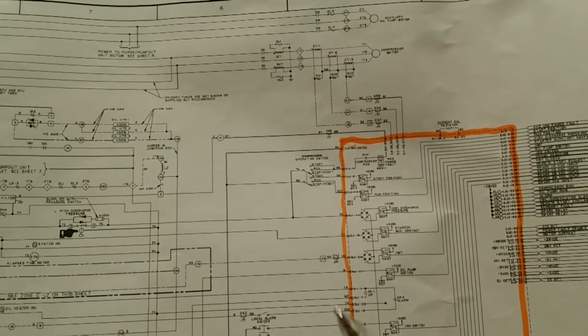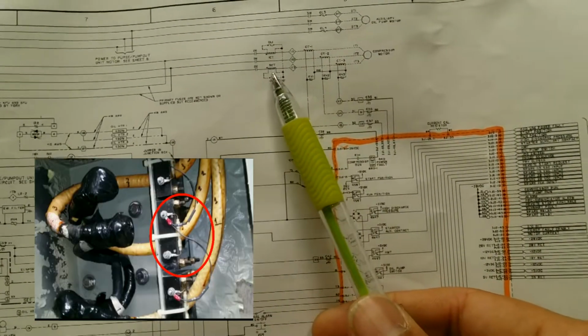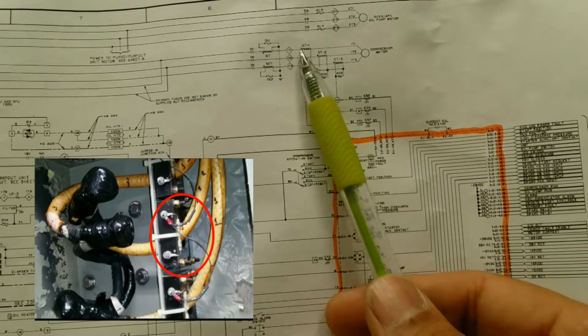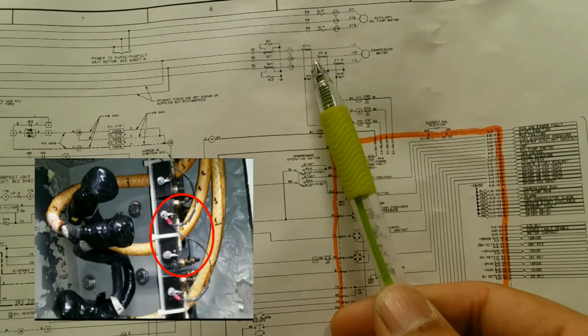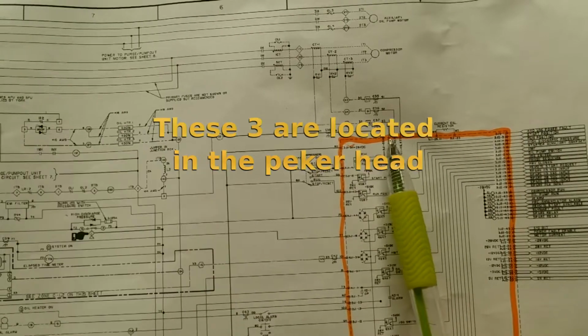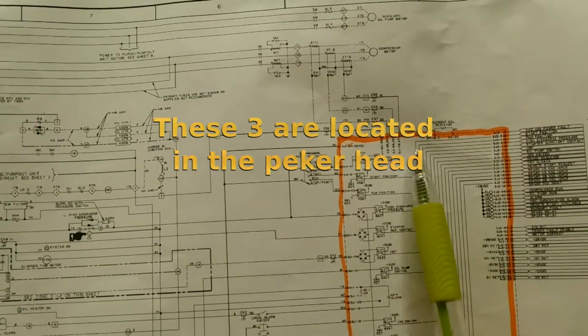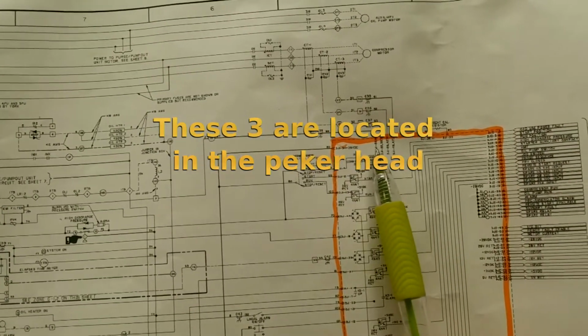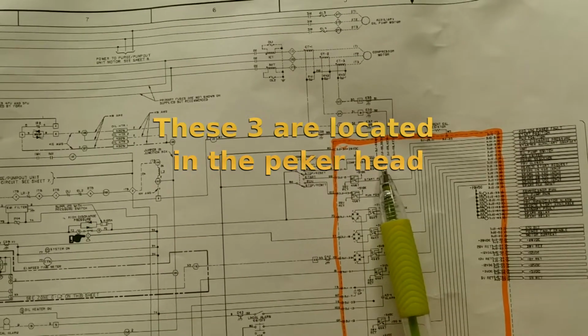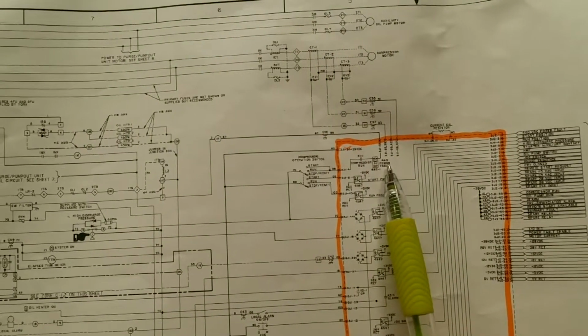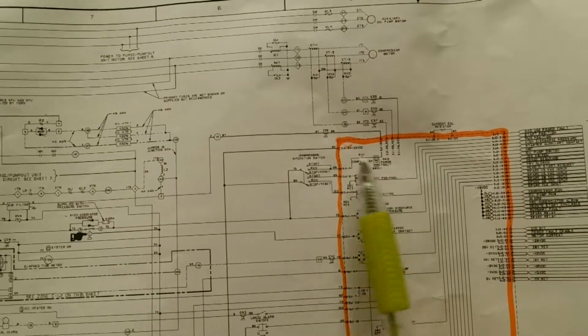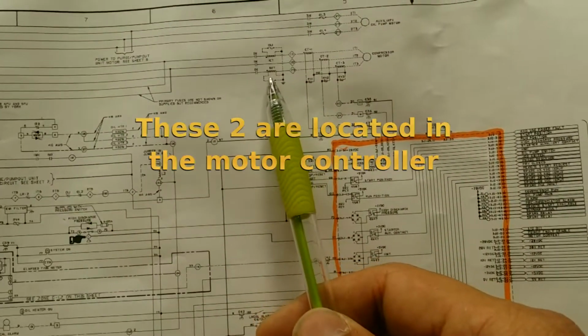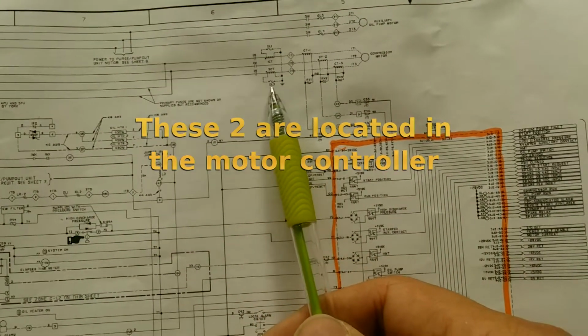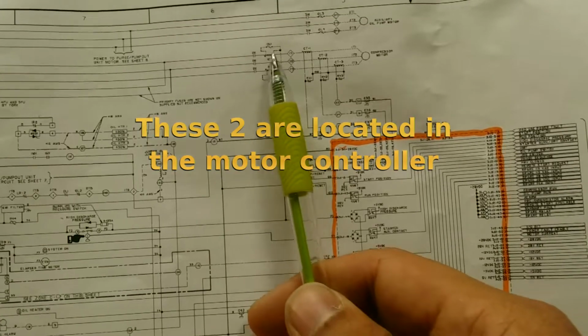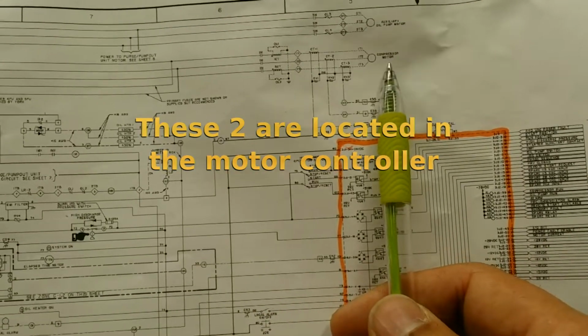And moving on to the current transformers, there are 5 of them. 3 of them provide direct input current signal into the input and output module. And that's how the system is able to display the current that it is consuming at the moment. And then the other 2 current transformers are wired in series with the overloads so that they can provide direct protection to the motor controller.